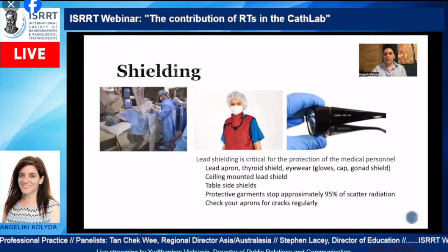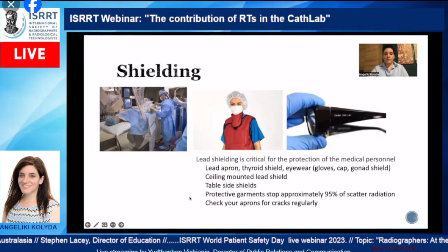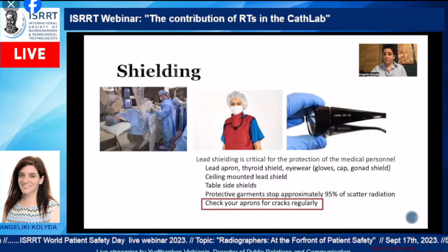As for the shielding, lead shielding is critical for the protection of the medical personnel. Lead apron, thyroid shield, eyewear, ceiling mounted lead shield, as you can see on the left image, table-side shields, and protective garments block approximately 95% of scatter radiation. And we have to check our aprons for cracks regularly. This is our job, of course, with medical physicists.